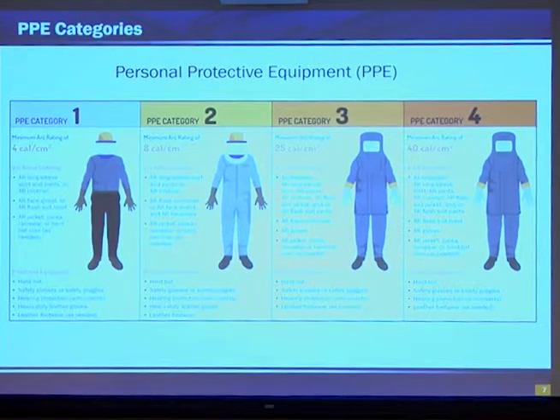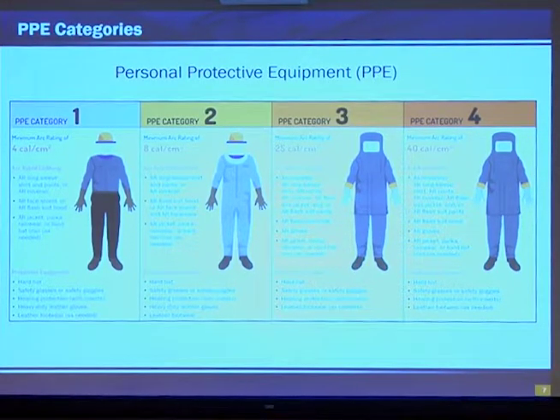When we move over to PPE Category 2, the incident energy rises from 4 calories per centimeter squared to 8 calories per centimeter squared. Everything else is pretty similar to Category 1. The main difference, looking at the picture, is we're going from a face shield to a full-on beekeeper suit. Well, sorry. But look at that guy, seriously. I mean, I want you to be protected. So you're going from Category 1, which is 4 calories per centimeter squared, to 8 calories per centimeter squared. So if you do elect to wear a face shield, you have to remember that you have to wear it with the balaclava. Everything else is pretty similar. You still have to wear your ARC-rated long sleeve shirt, your pants, your coveralls, your hard hat, your safety goggles.